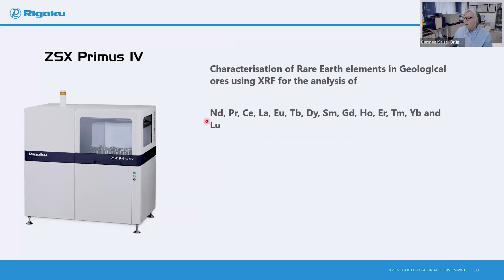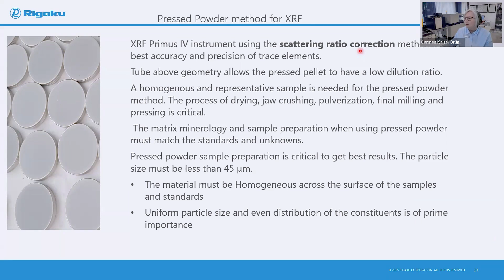So, of course, we have to start with the sample preparation. And, of course, in most cases, we will use the pressed powder method for preparation. So very important is to have the correct particle size. And, of course, we need to have homogeneity within the pressed powder. So the pressed powder method suffers from matrix and mineralogy errors. So we need to try to make use of the fundamental parameters method. We can also use in our software something which we call the scattering ratio correction method. So it helps us to improve basically the method for best accuracy and precision for these trace elements.